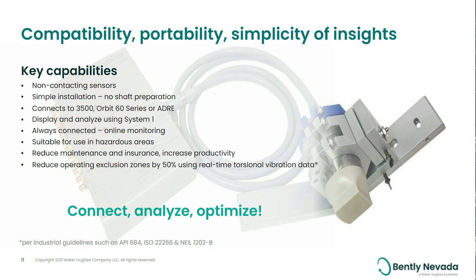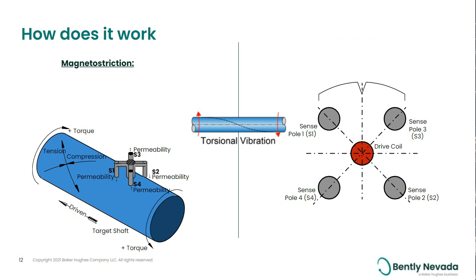So how does the sensor work? How is this non-contacting? Well, the theory of operation is actually relatively straightforward, and it's based on magnetostriction. What that means is as you take any metallic shaft and apply a torque, the magnetic permeability will change. That's a natural phenomenon we count upon in order to measure torque and torsional vibration.